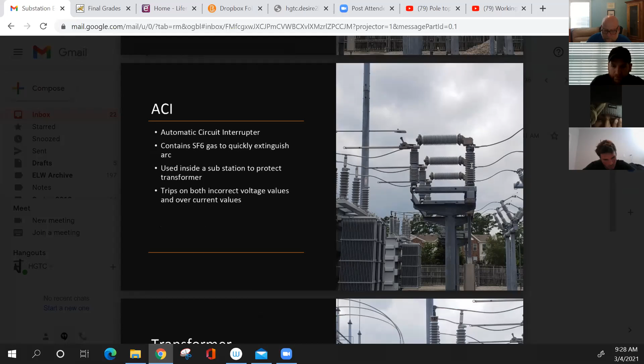I've had to open and close a couple of switches similar to this, and there's an indicator on there that tells you if the cylinder is full of gas or if it has leaked out. You don't want to open that switch if there is low gas in it, because that could cause an explosion inside that tube. So you want to be real careful. Make sure before it's operated that the tube has the right amount of gas in it. If not, report that to your substation maintenance people, and they'll come in and do maintenance on the switch itself. So that's an ACI, automatic circuit interrupter. Do you have any questions about the ACI, guys?